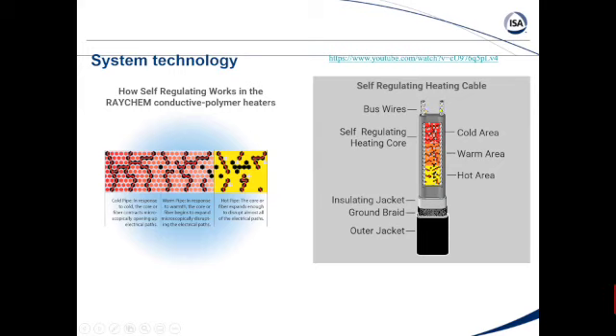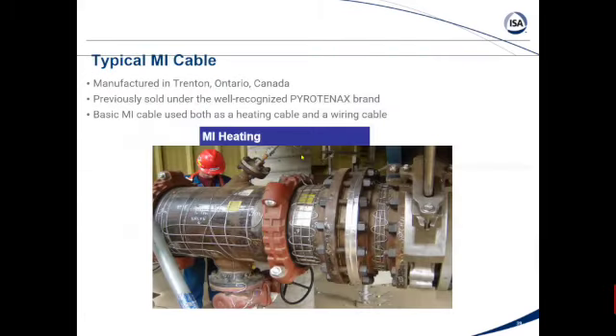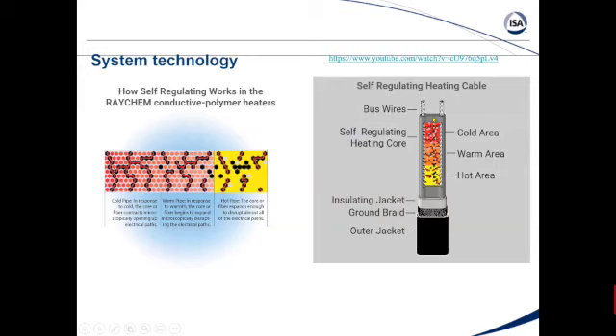These two conductors here are strictly current carrying conductors. They're not heating elements. They are not resistors in any way. They are just delivering power down the run of the cable. The actual heating element is this extruded material. When you open up this cable, it looks like a black plastic, and that's actually a semiconductor, and that's really what's creating the heat. So what's going on here is, when this black plastic is extruded through these two conductors, let's say it's 120 volts and there's your neutral, you have conductive paths going between here and that conductor all along the length of this cable. Now the conductivity of that heating core changes based on temperature. When it gets cold, it contracts, and it becomes more conductive, creating more heating elements all along the length of that cable. When it gets hot, it expands, creating less conductive paths, therefore putting out less heat. So that's how the cable self-regulates itself.